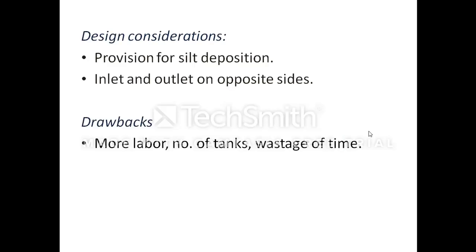For the design considerations of the fill and draw type sedimentation tank: provision is made at the bottom for silt deposition. The outlet should be above the silt zone so that silt is not removed through the outlet. The inlet and outlet should be on opposite sides. The problems with this type are that more labour and more tanks are required, and there is wastage of time in filling, emptying, and cleaning the tank.